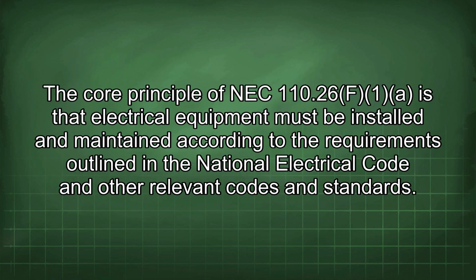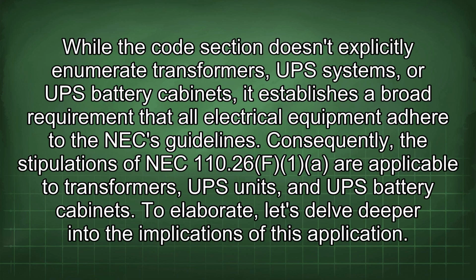The core principle of NEC 110.26 is that electrical equipment must be installed and maintained according to the requirements outlined in the National Electrical Code and other relevant codes and standards. While the code section doesn't explicitly enumerate transformers, UPS systems, or UPS battery cabinets, it establishes a broad requirement that all electrical equipment adhere to the NEC guidelines. Consequently, the stipulations of NEC 110.26 are applicable to transformers, UPS units, and UPS battery cabinets.